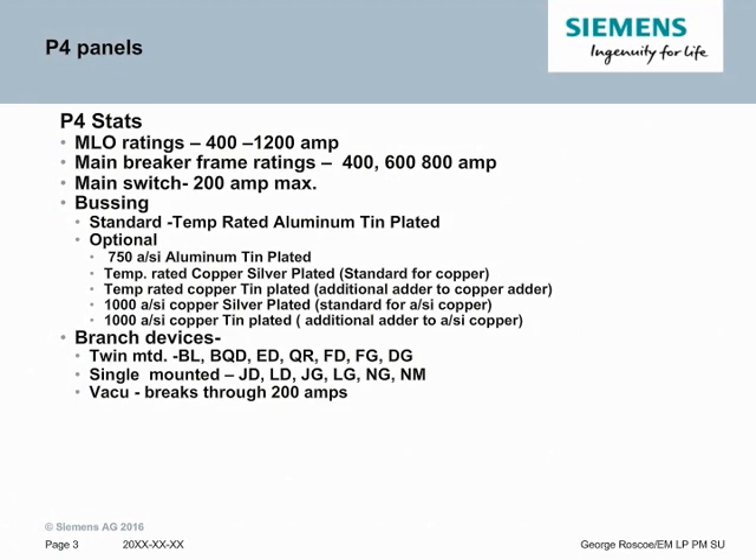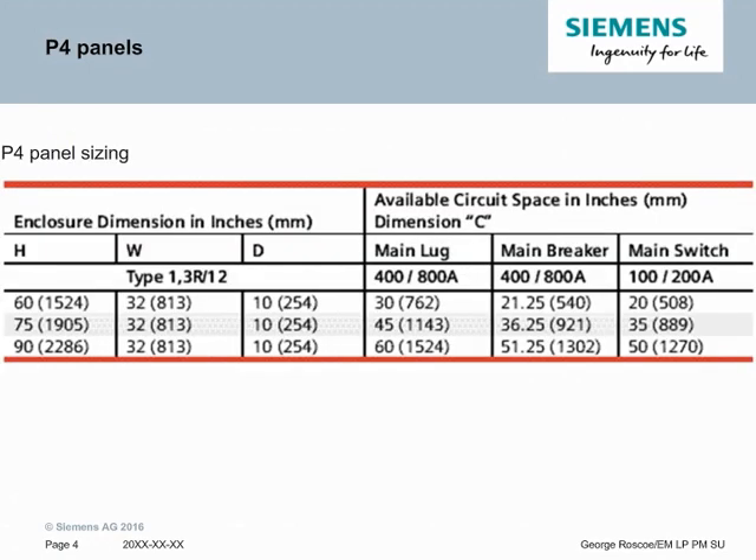For branch devices, we can twin mount up to 250 amp breakers including our FD and FG lines. We can single mount all the way up to 800 amp breakers in one section. We also allow Vacu-break switches through 200 amps to be mounted as feeders. There are three standard sizes for P4 panels — sizing is dependent on the number of feeders and main breakers as well as features required. The heights are 60, 75, and 90 inches high, and the width and depth are consistent throughout.